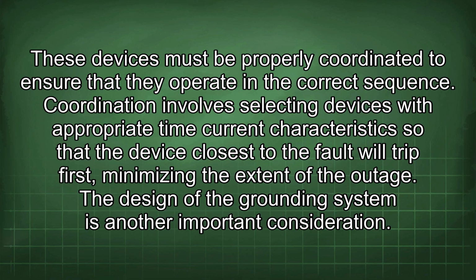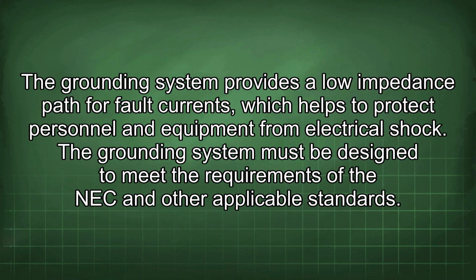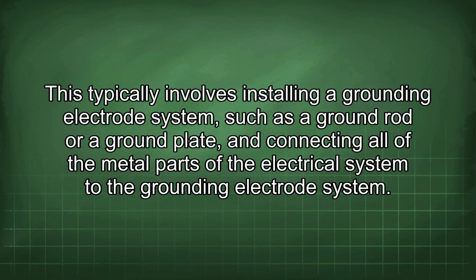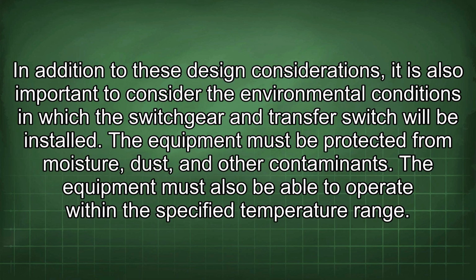The design of the grounding system is another important consideration. The grounding system provides a low impedance path for fault currents, which helps to protect personnel and equipment from electrical shock. The grounding system must be designed to meet the requirements of the NEC and other applicable standards. This typically involves installing a grounding electrode system, such as a ground rod or a ground plate, and connecting all of the metal parts of the electrical system to the grounding electrode system. In addition to these design considerations, it is also important to consider the environmental conditions in which the switchgear and transfer switch will be installed. The equipment must be protected from moisture, dust, and other contaminants. The equipment must also be able to operate within the specified temperature range.